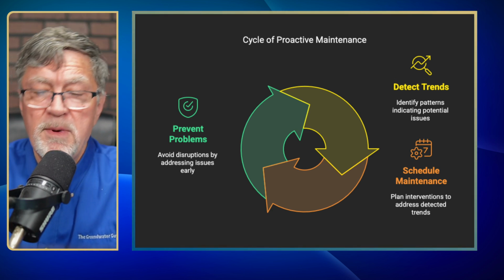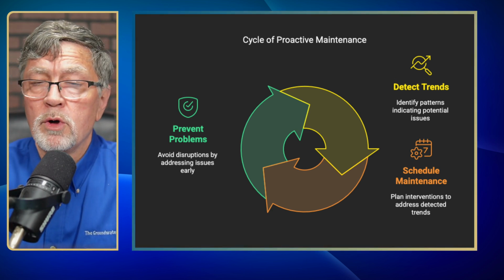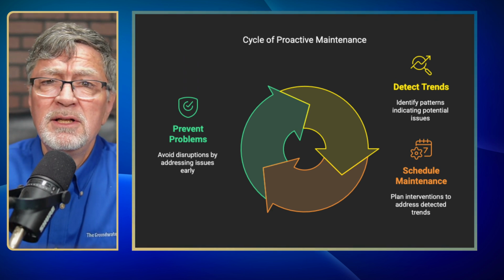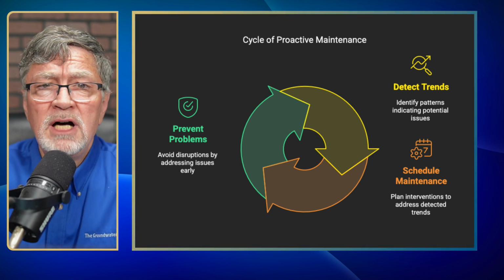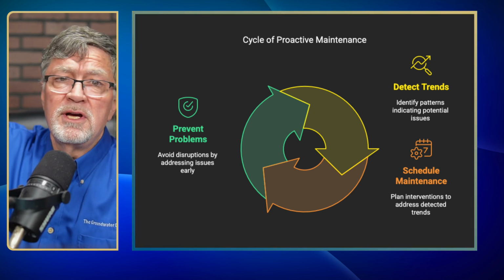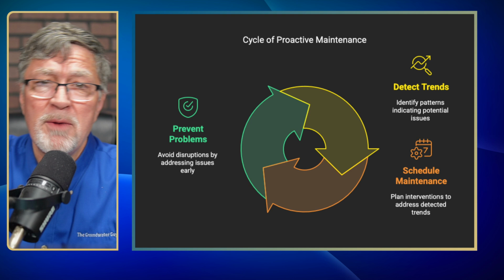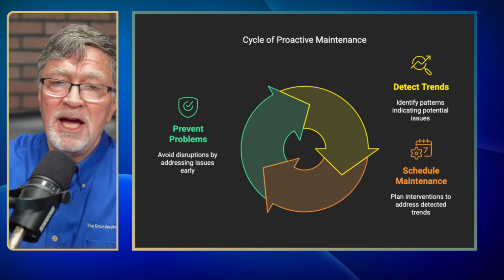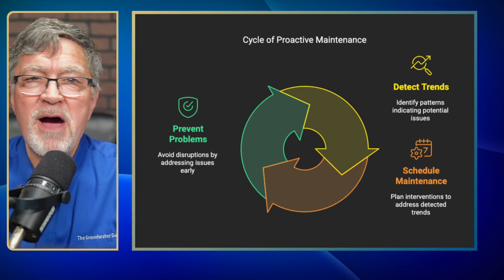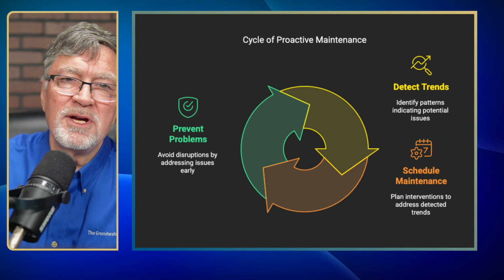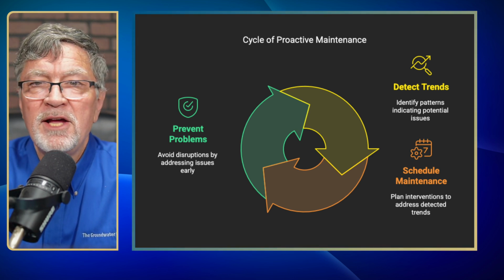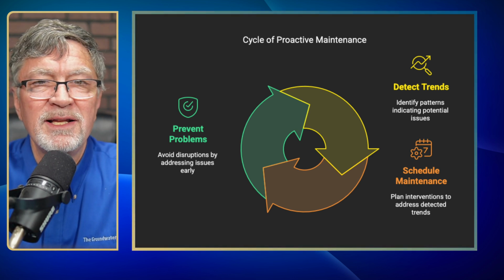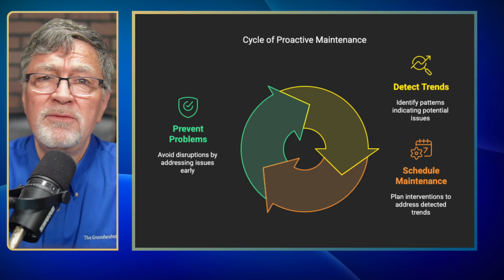Then that cycles back around again, and we start looking at the trends again. So your long-term trends: once you fix things and get that vibration down in the pumps, your charge is going to be back down again, and then that trend starts up again. It's always about looking at the data and making data-driven decisions.